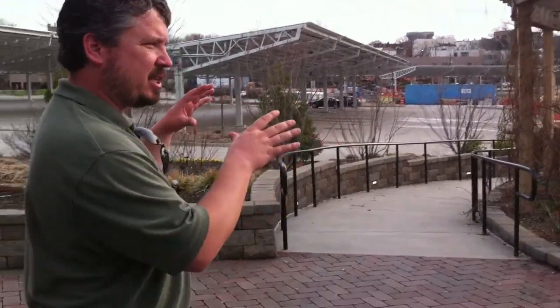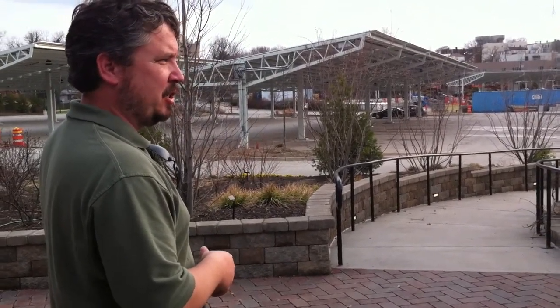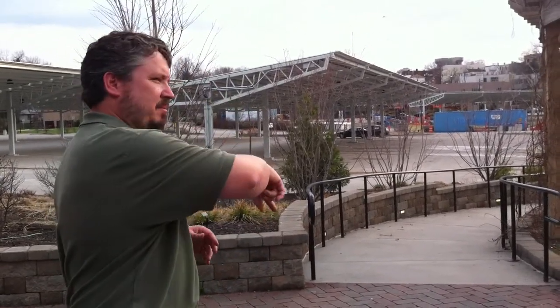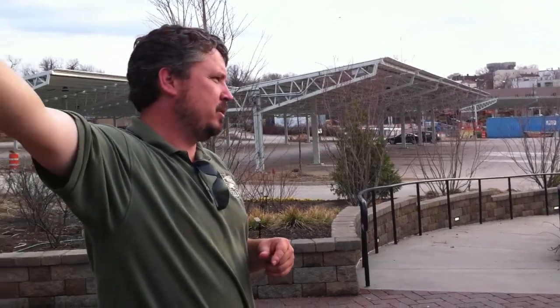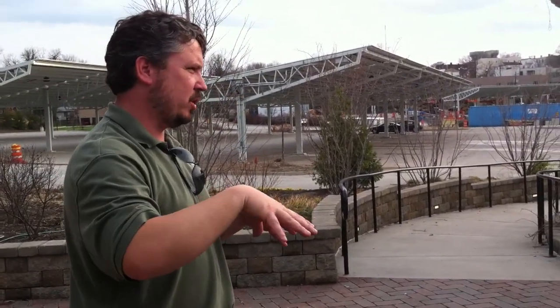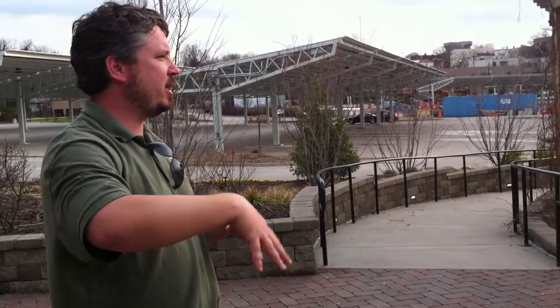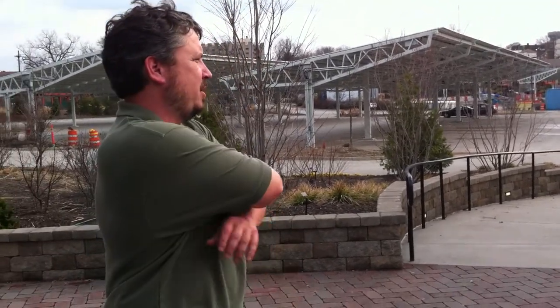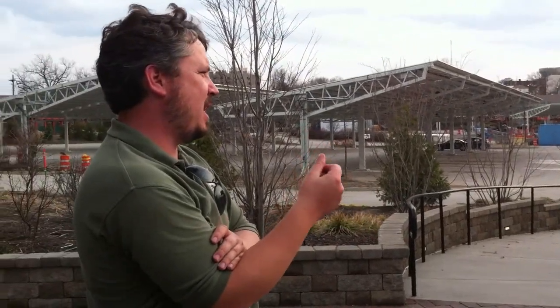You can't just take the 1.6 megawatts and run it up the local utility pole. It doesn't work like that. You have to use it the way we're set up in Ohio right now. So we had to get this power up through this building, up under the bridge, all the way back into the middle of the zoo through existing electrical infrastructure. So of course, with 1.6 megawatts, all our transformers were too small. So we upgraded, everything had to be redone. It was $500,000 just for wire and transformers. So again, something you normally wouldn't have. So $2.5 million right off the top.